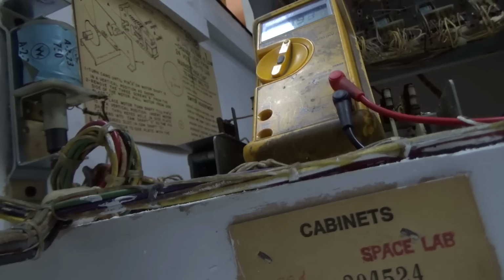One way to know if you've got a bad transformer: you might see a bunch of wax-looking stuff laying on the bottom of the cabinet underneath the transformer. I don't mean a little paste, I mean big heaps of stuff that looks like candle wax dripped out of the transformer. What's happened is the transformer got so hot that it started to melt, and that's what you're looking at. That will kill the transformer.